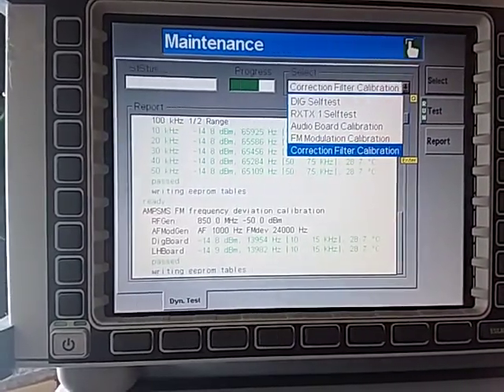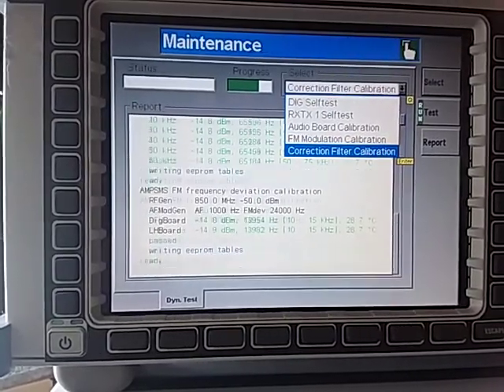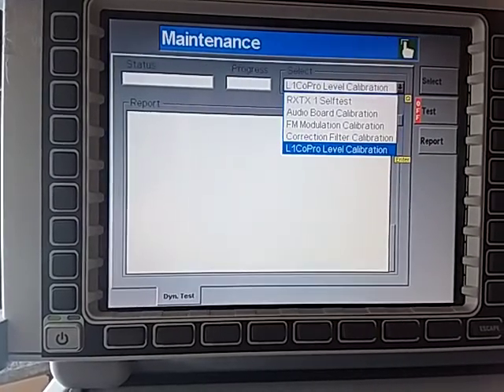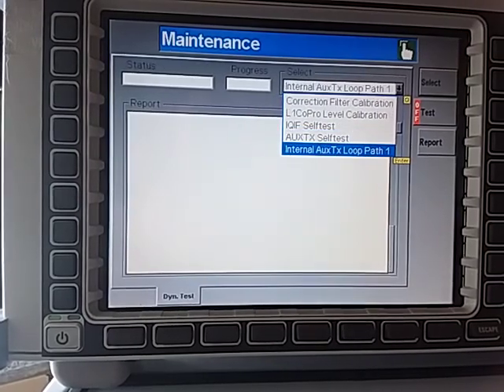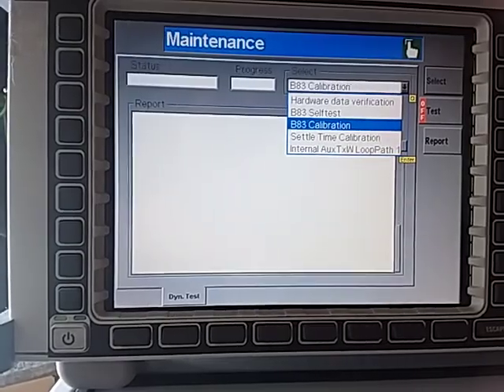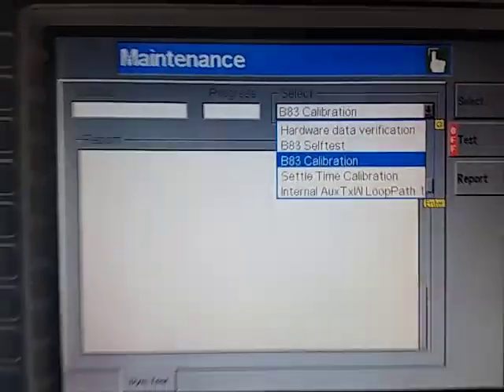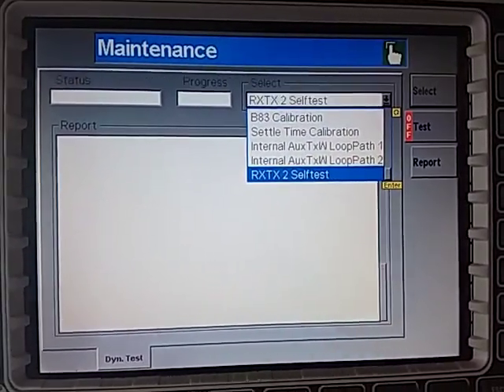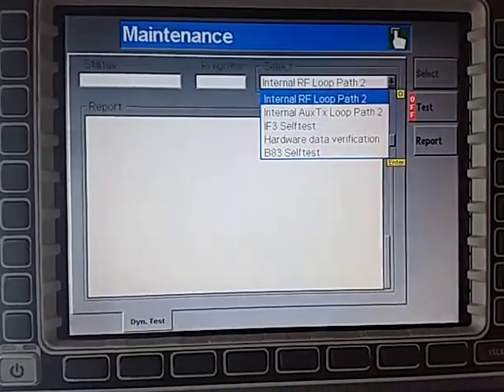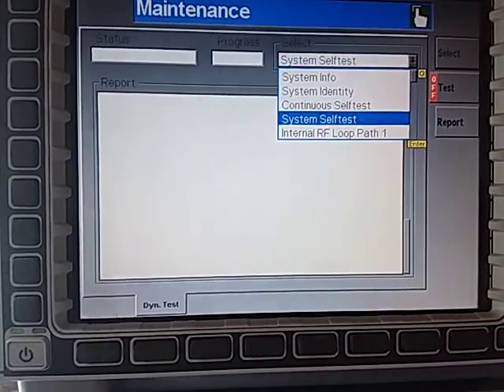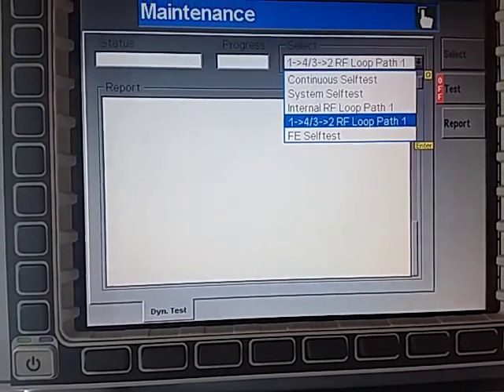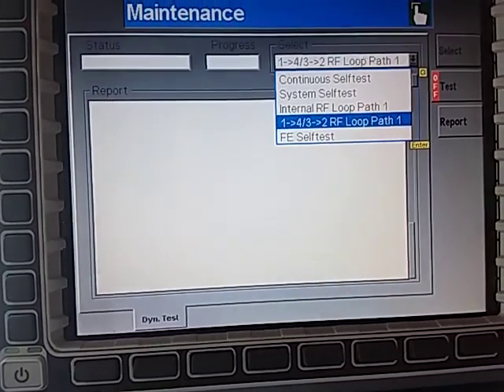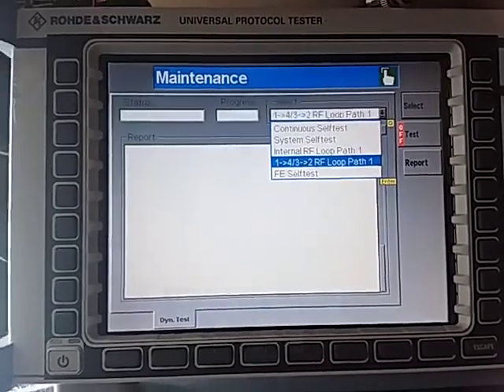Correction filter calibration, I don't have that, it just needs an accessory to do that. You're best to look at your documentation on that. That's pretty much the only other ones you need to look at. That is the B83 which is another option which takes ages to look at. I wouldn't be too worried about running any of these. The main ones as I've said are the system self test, the internal loopback test, and the 1432 RF external loopback test. Those are the main things you should be looking at to check that your analyzer's in good health.